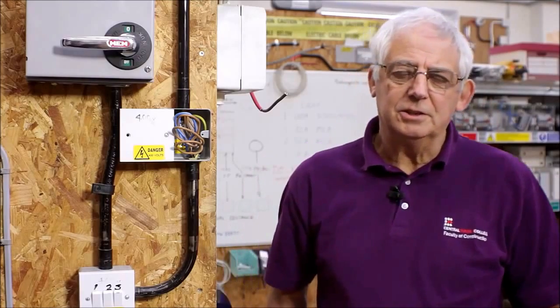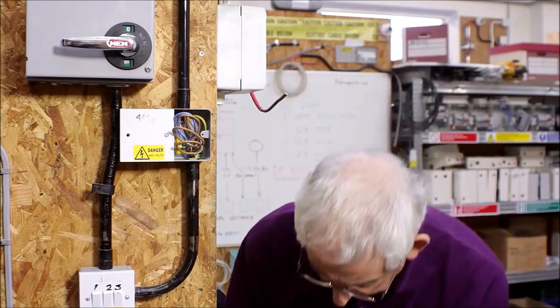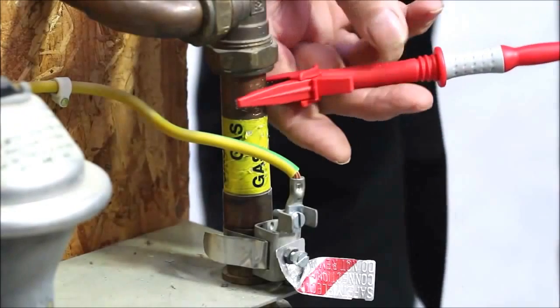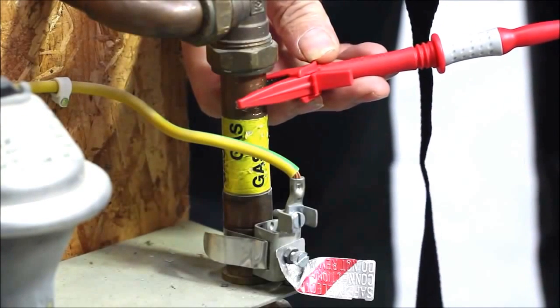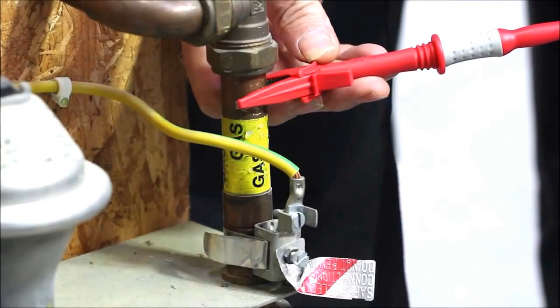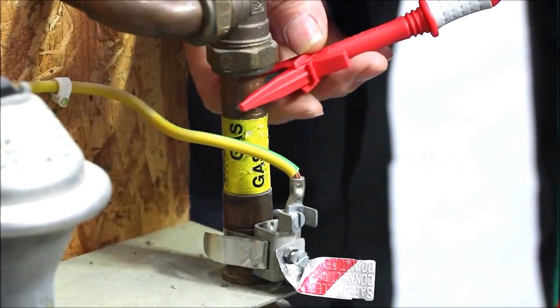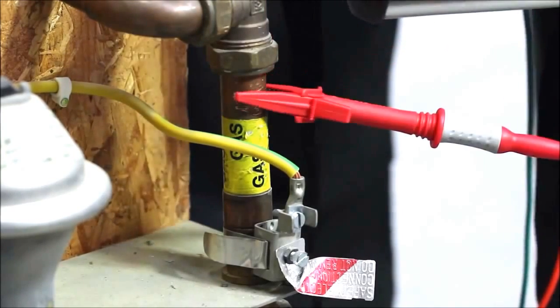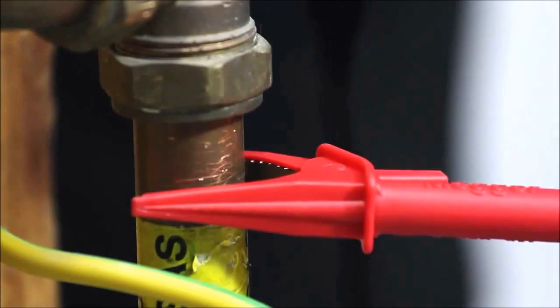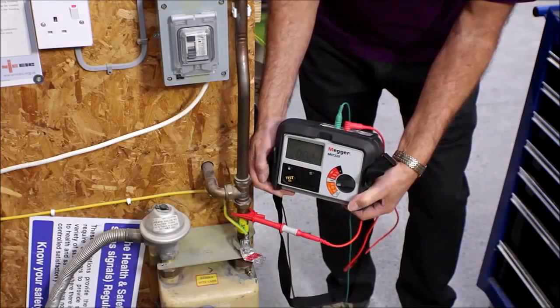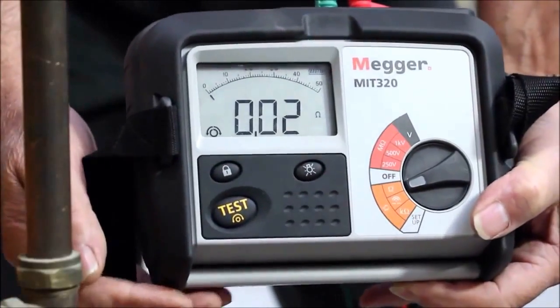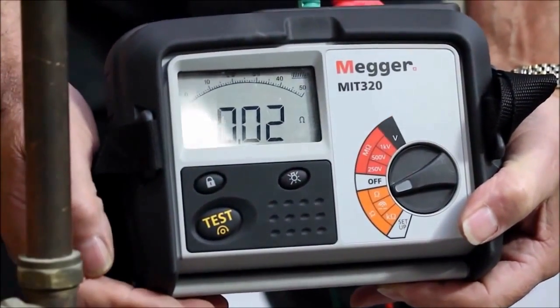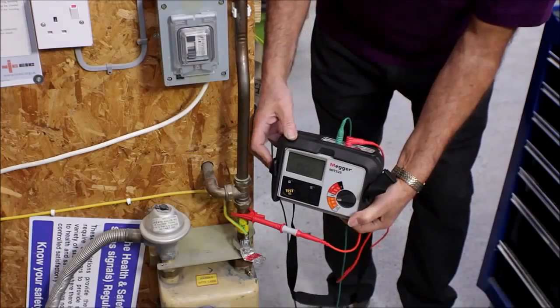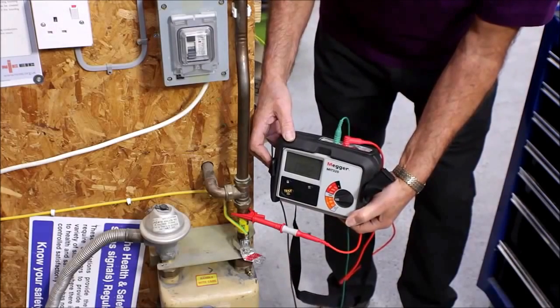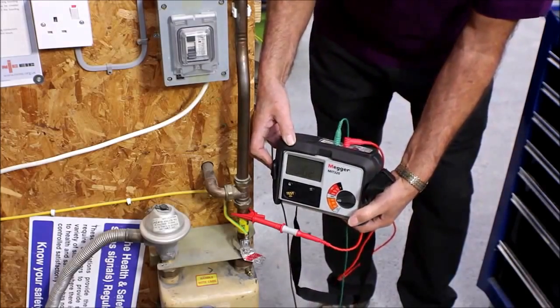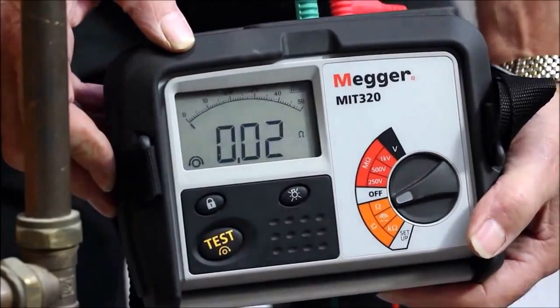Whenever I do this test, I prefer to use a connection on the pipe work rather than the clamp, because what that's telling me now is that the integrity of the clamp is very good. There's a good joint between the clamp and the pipe. If there was dirt or corrosion underneath it, the resistance would probably be quite high. So you can see now I've got a reading of 0.02 ohms, perfectly acceptable for this installation. As I said, the value that we should be thinking of is 0.05, so this is quite low.